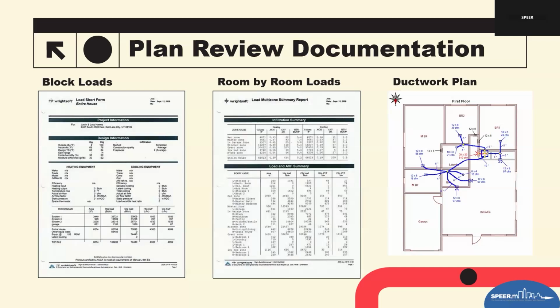And then of course, as we said earlier, duct sizes and airflow values for each one. A trunk and branch layout, that's what this simplified plan is. We see the size of the trunk and then the size of each branch. We also see little triangles, hopefully there'll be some kind of Y. They won't be just a duct board triangle, but it probably is. And the one at the bottom looks like it's going to be another plenum, branched off from there. So just making sure those things are done.